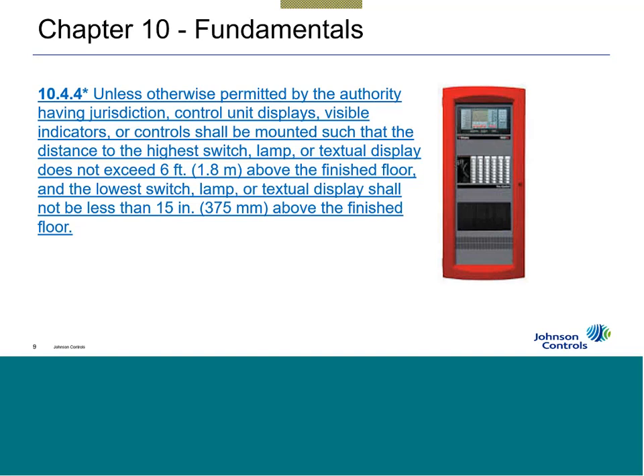So now what we're talking about is not the cabinet itself, it's the control unit display, visible indicators, LEDs, the switches, the things that you interface with. They can be no higher than 6 feet. So right here, the top of this display can be no higher than 6 feet. And then likewise for the bottom part, the switches and LEDs can be no lower than 15 inches off the finished floor. So again, it's not the cabinet, it's what you interact with, you interface with: 6 feet and 15 inches.